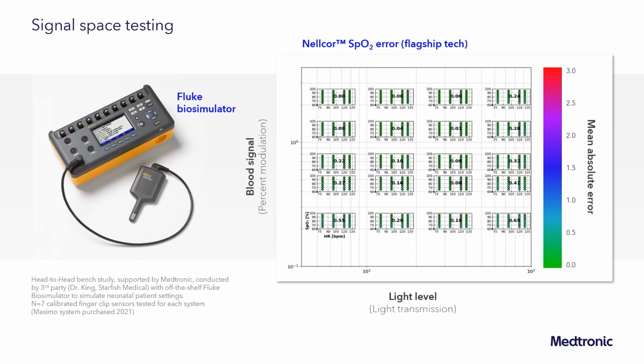One of the ways that we ensure our products do that is we go back to that signal space that we had talked about. And in that signal space, we will test our pulse oximeters. One way to do it is with a Fluke biosimulator that has an SpO2 functional tester. What this does is it generates optical signals that match certain light levels and certain percent modulations. With those optical signals, we can look at our device and ensure that it's performing as expected.